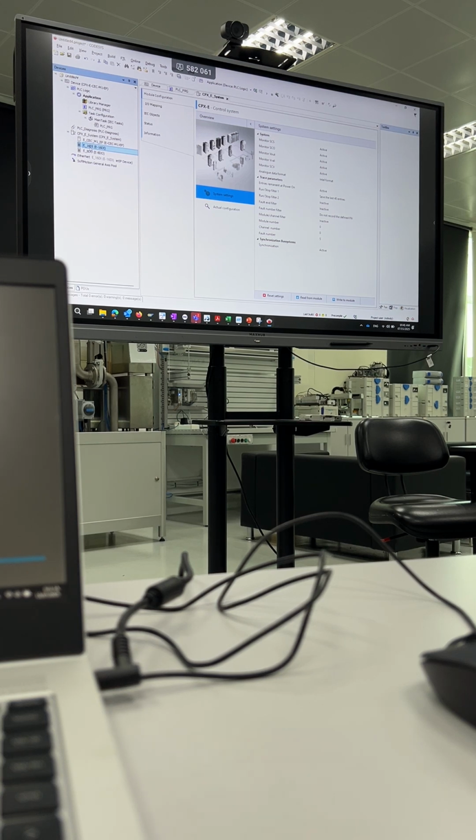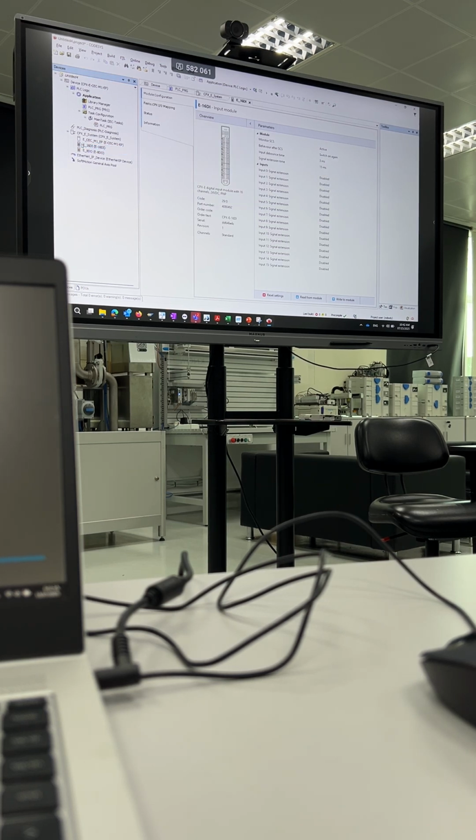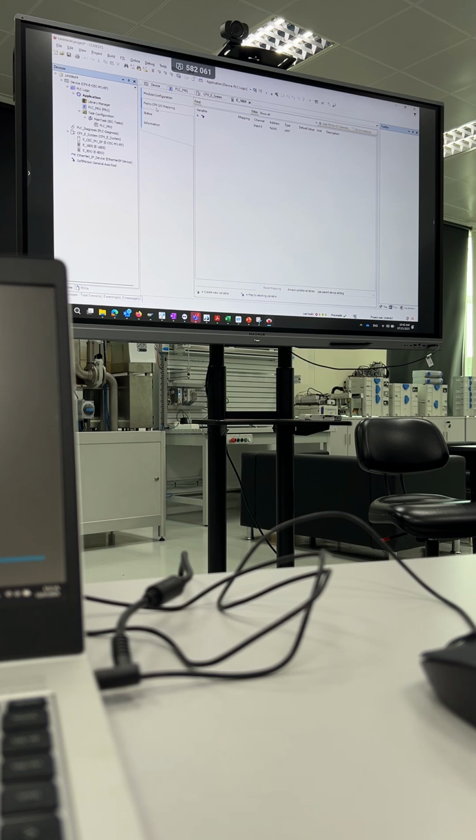This only applies to the I/O module that is attached to the PLC. If let's say you have an EtherCAT slave and then the I/O module in the EtherCAT slave, you can also scan it, but it's a different way to do it. So right now, if we want to read the digital input or digital output, you already have an I/O mapping for it. So these are the addresses for you.